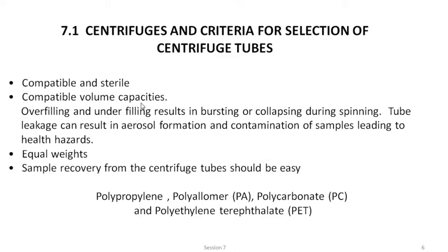Next, it should be compatible with volume capacities. Say you have a sample which is around 10 ml, and if you have a centrifuge tube of 1 ml, how will that possibly work out for you? You will have to do it 10 times, right? Whenever you choose, you have to see that you have compatible volumes and its capacity should be what you desire to separate. So you are not supposed to overfill it or underfill it.